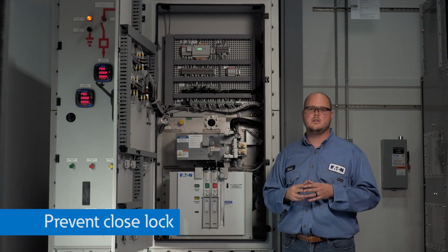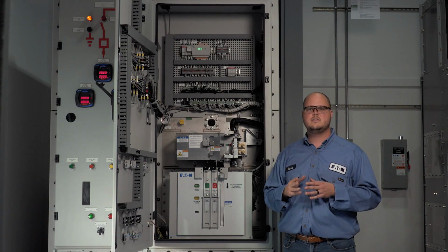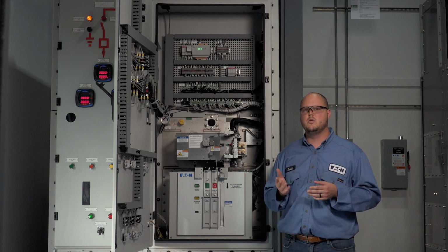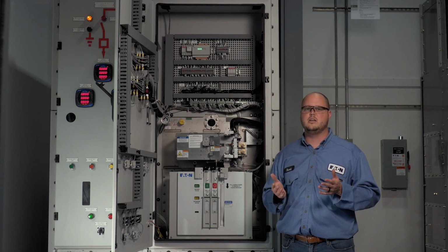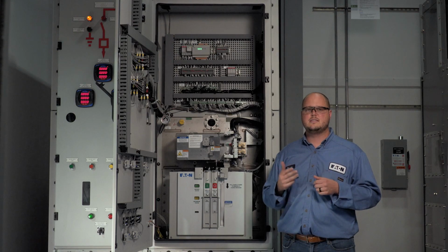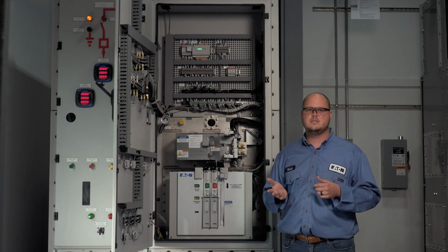I will first demonstrate the prevent close lock. This is used to prevent anyone from closing the 3-position switch. This is an especially useful feature for spare breakers that should remain isolated or grounded while not in use, or when taking a lineup out of service. This is common in main configurations and applications with redundant lineups.